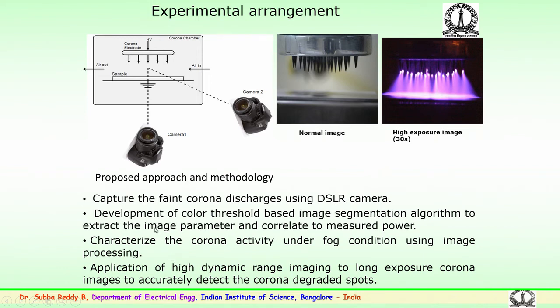Initially, to capture the faint corona discharges, these DSLR cameras were used with decided camera settings and capture time. Then a color thresholding based image segmentation algorithm was developed, particularly to extract the image parameters and correlate them to the measured power, that is the power which we have measured in the laboratory.